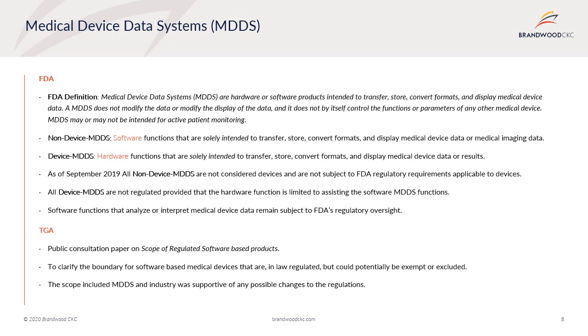All device MDDS are also not regulated, provided that the hardware function is limited to assisting the software functions for electronic transfer, storage, conversion of formats, or display of medical device data. However, software functions that analyze or interpret medical device data in addition to transferring, storing, converting formats, or displaying clinical laboratory tests or other device data remain subject to FDA's regulatory oversight. The TGA also released responses to a public consultation paper on the scope of regulated software-based products, seeking industry feedback to clarify the boundary for software-based medical devices that are regulated but could potentially be exempt or excluded.